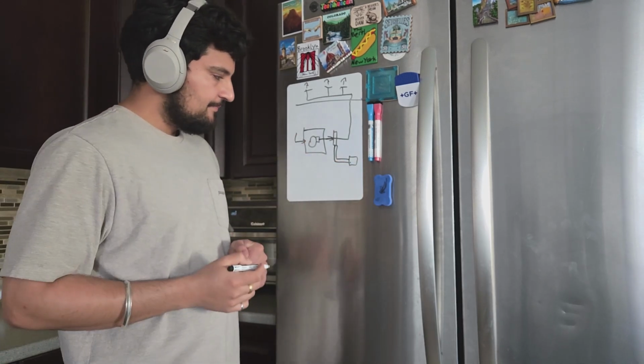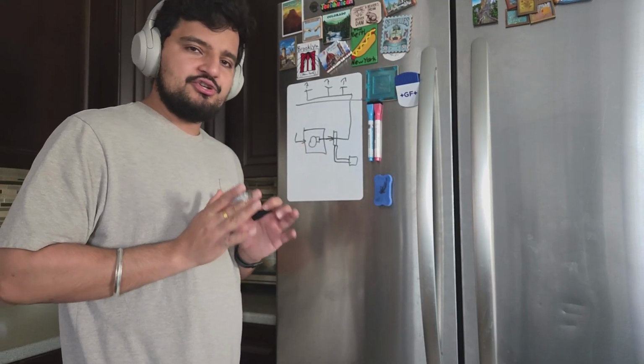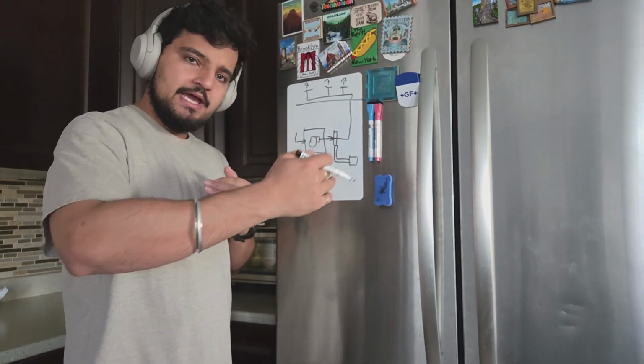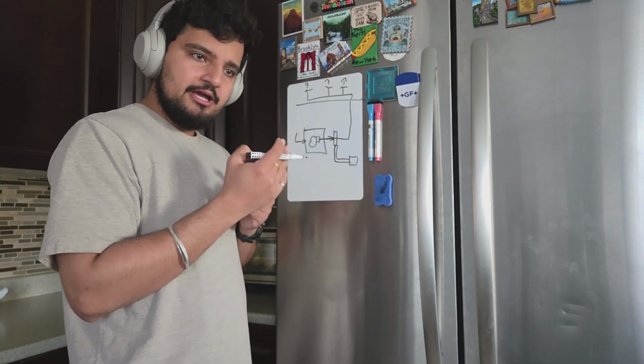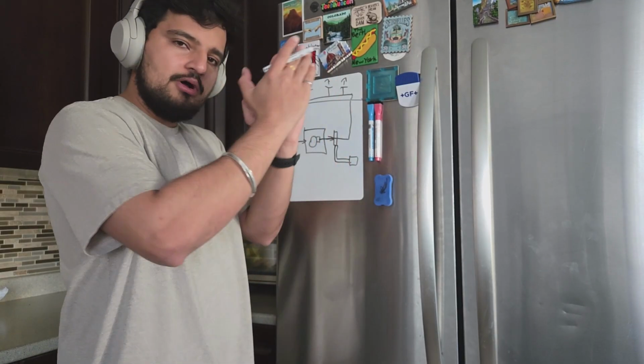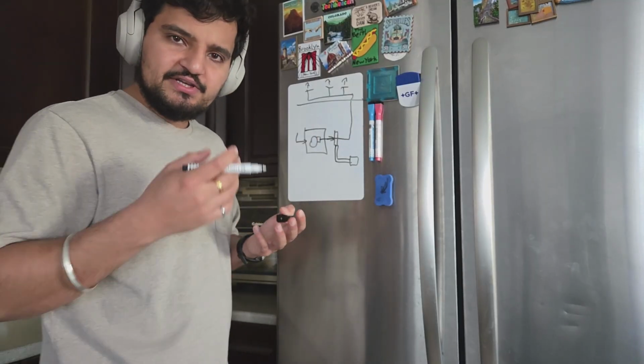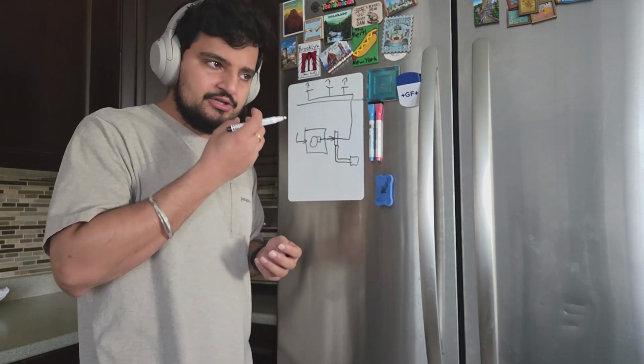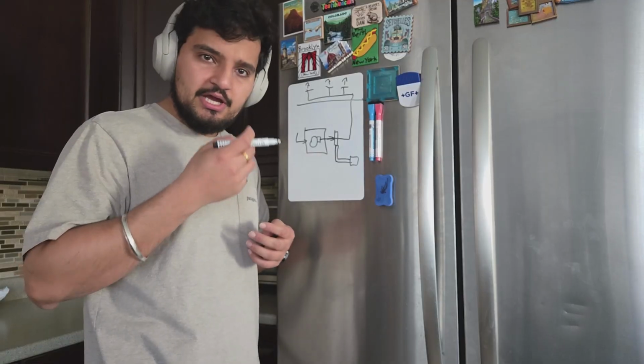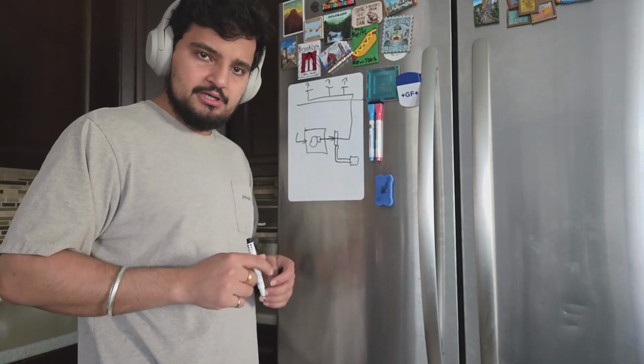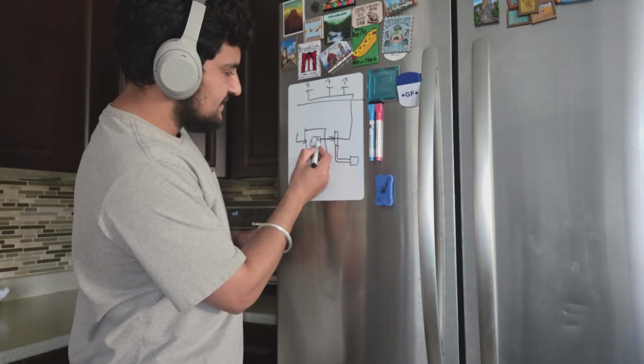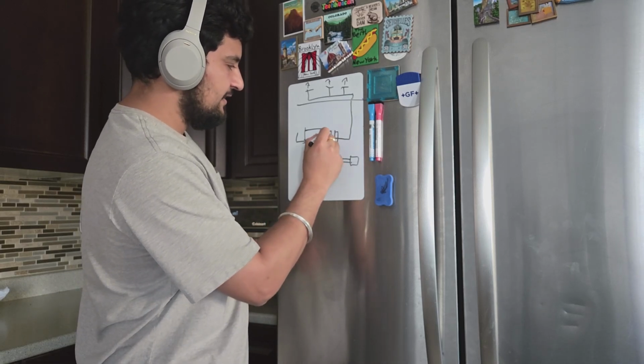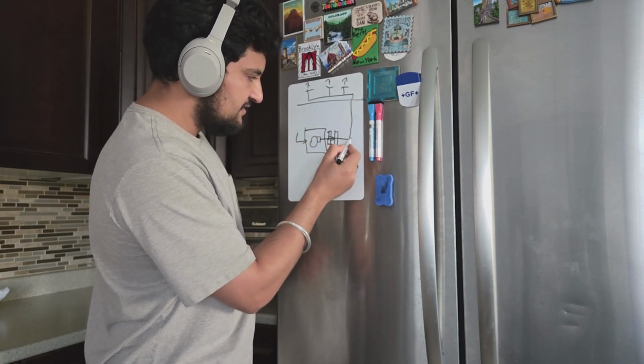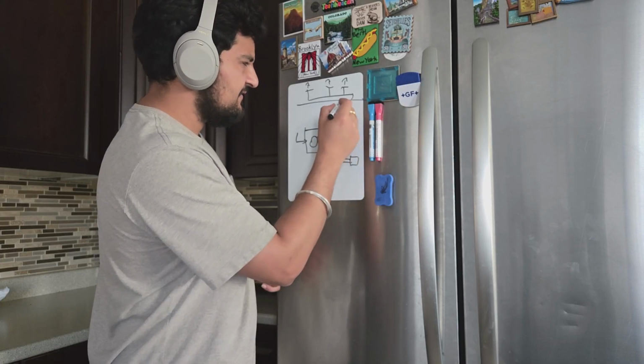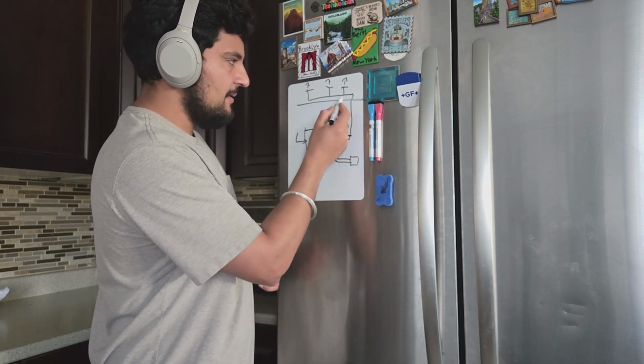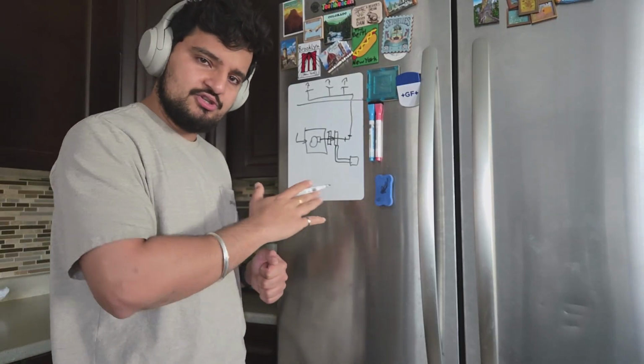So this fan can function at a certain pressure drop, right? So the fan is able to generate a certain amount of positive pressure that helps the air push through all that ductwork into your house. Think of it like using a straw to drink a smoothie, for example, right? You need to create a certain amount of pressure inside that straw for that smoothie to travel up. So same idea here. So as this fan is pushing air, it has to go through the filter, through the cooling coil, through these ducts that have elbows and stuff like that. And everything here generates a bit of pressure loss as the fan pushes the air through the system, right?